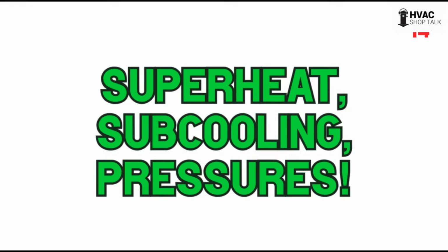Superheat, subcooling, refrigerant pressures. Airflow changes all of them. You get low airflow, it's going to cause your superheat to dive, especially on an orifice system, which is fixed, not a TXV, not an EEV. Any fixed system, orifice, low airflow is going to cause the superheat to dive. It may be zero. A lot of times if you have a junky coil, bad blower, you're going to be in a freeze-up situation real fast, but your superheat will dive.